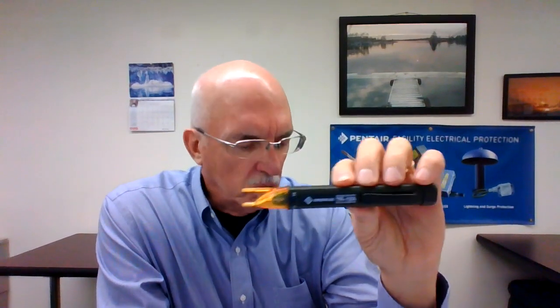So there's two types of proximity testers, and never trust a proximity tester. The only time I trust it is when it tells me something's hot. When it tells me something's hot, I believe it. When it tells me something's not hot, I don't believe it. So what you have to do, with these proximity testers, both this one and the Milwaukee, is test it on a known live circuit.